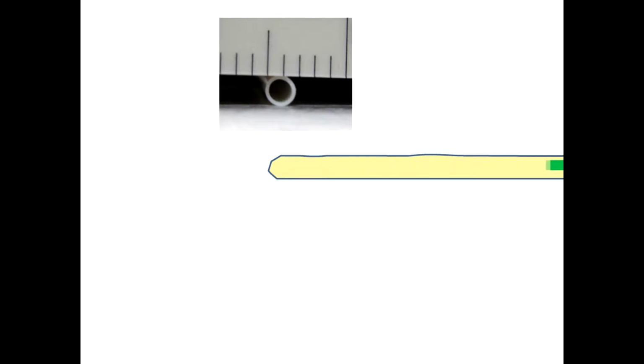The mold probe used for transportation of the source has an outer diameter of 1.8 mm and a wall thickness of 0.15 mm. The source capsule diameter is 0.9 mm itself, and its uncertainty inside the plastic tube we estimate as plus minus 0.25 mm. If we create a turn of the mold probe, we make an effect of pressing down the active part of the source cable to the lower wall of the probe, reducing in this way the uncertainty of the source positioning down to 0.1 mm. The mold probe is tightly fixed to the base plate.